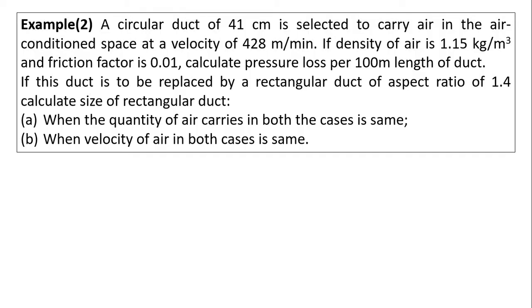In the second numerical we consider the opposite case: the dimension of a circular duct is given and we have to replace it with a rectangular duct. A circular duct of 41 cm diameter carries air at a velocity of 428 m/min. If density of air is 1.15 kg/m³ and friction factor is 0.01, calculate pressure loss per 100 m length. If this duct is replaced by a rectangular duct of aspect ratio 1.4, calculate the size of rectangular duct for both criteria.